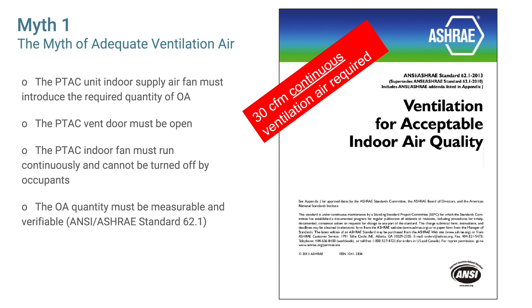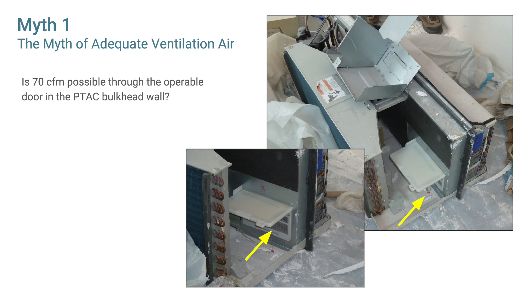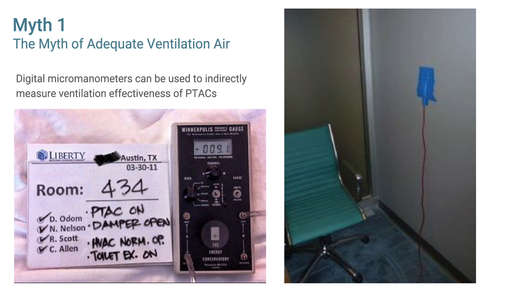The outdoor air quantity must also be measurable and verifiable, which is often very difficult with typical test and balance methods. The picture shows the typical outdoor vent in the bulkhead separating the indoor and outdoor sections of the PTAC chassis. Some manufacturers claim 70 CFM is possible through the operable door, but this may be achievable only in factory bench tests. In our field testing using micromanometers, we estimate you need at least plus five pascals of positive pressure in a hot humid climate to prevent mold and moisture problems.